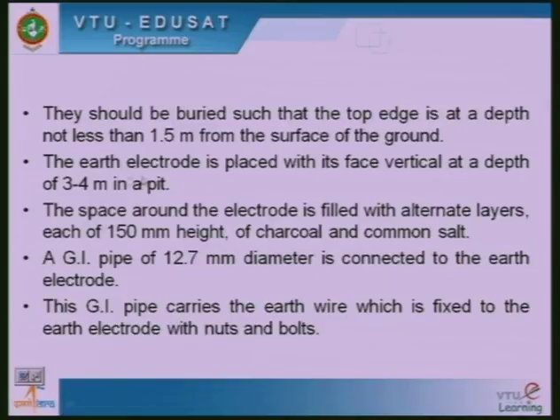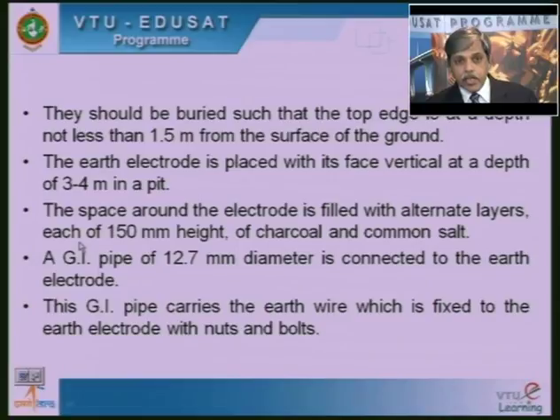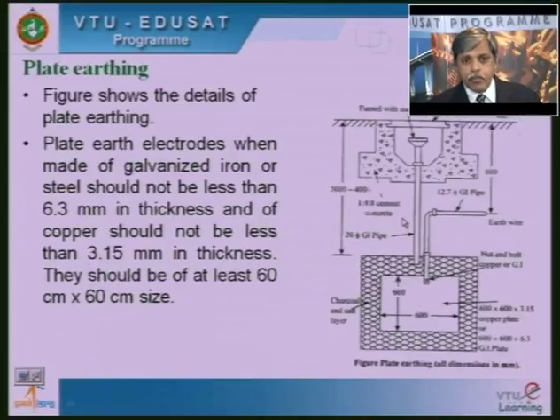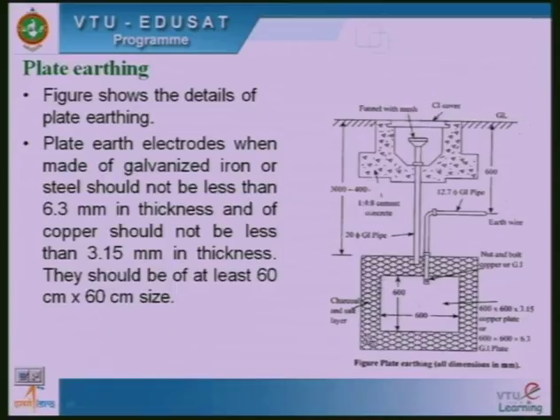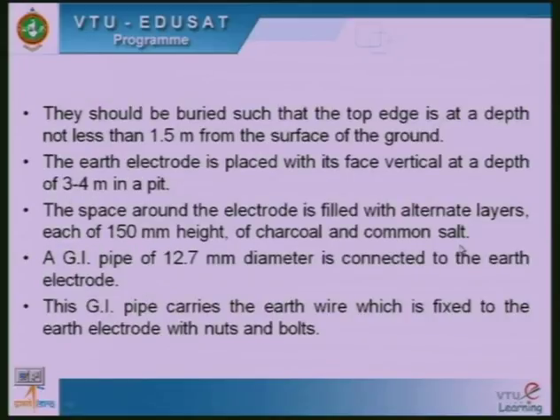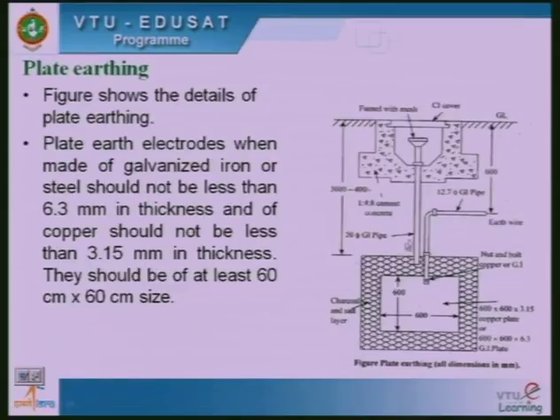1.5 meters. The earth electrode is placed with its face vertical at a depth of 3 to 4 meters in a pit. The space around the electrode is filled with alternate layers, each of 150 mm height, of charcoal and common salt. In this diagram, these are the different layers of charcoal and common salt. A GI pipe of 12.7 mm diameter is connected to the earth electrode. You can see here, this is a GI pipe connected to the earth electrode.